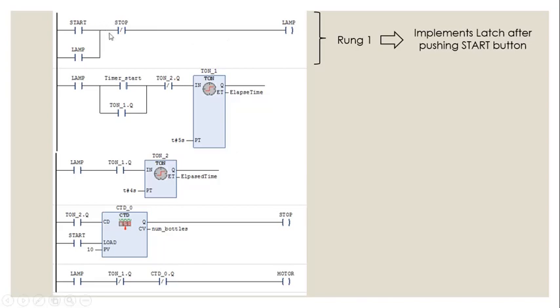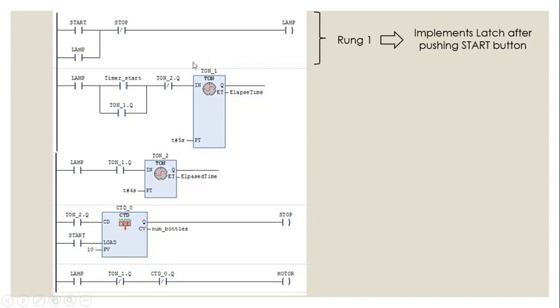This is a very basic example of how you can implement a latch in PLC. You momentarily press the start button and it will remain on. The stop button is normally closed, so if it is zero the conduction path will be there, turning on the lamp. Turning on the lamp provides an alternative path to keep it on. If the stop button is now momentarily pressed, the conduction path will not be there and the lamp will be off. So you have the start button to start the system and the stop button to switch off the lamp.